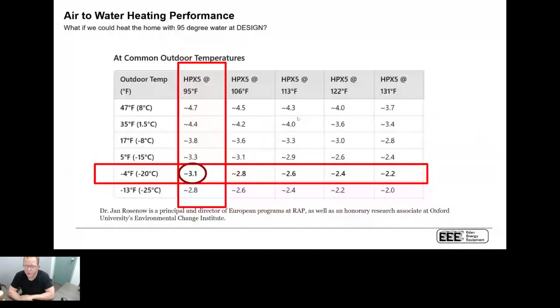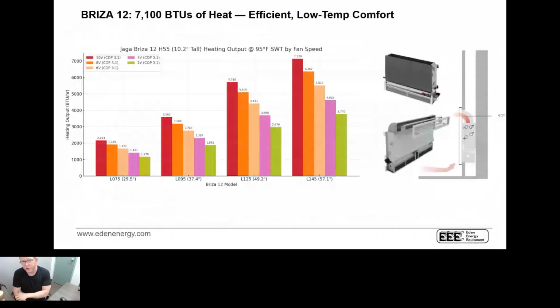So the way they're doing this is they're using low temperature emitters, and these emitters use 95-degree water. Just as a reminder, with 95-degree water at minus 20 degrees Celsius, we have a COP of 3.1. Had it been an air handler, it would probably have been a COP of 2 or a COP of 1.8. So we've gone a different route to try to increase the efficiency.